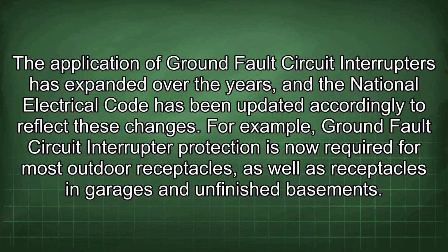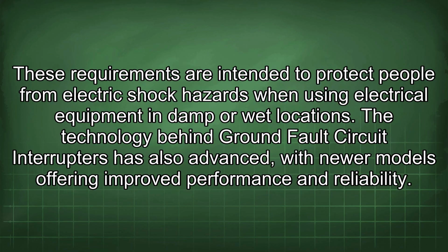The application of ground fault circuit interrupters has expanded over the years, and the National Electrical Code has been updated accordingly to reflect these changes. For example, ground fault circuit interrupter protection is now required for most outdoor receptacles, as well as receptacles in garages and unfinished basements. These requirements are intended to protect people from electric shock hazards when using electrical equipment in damp or wet locations.